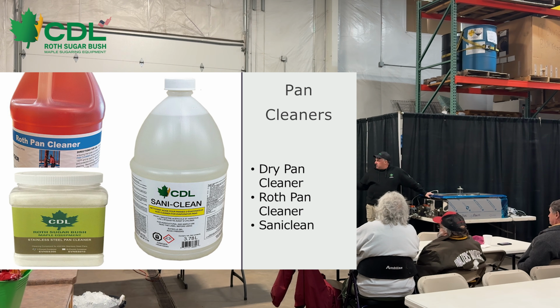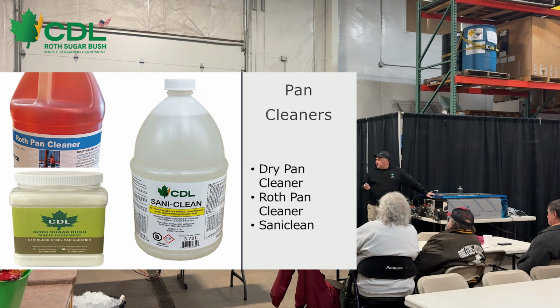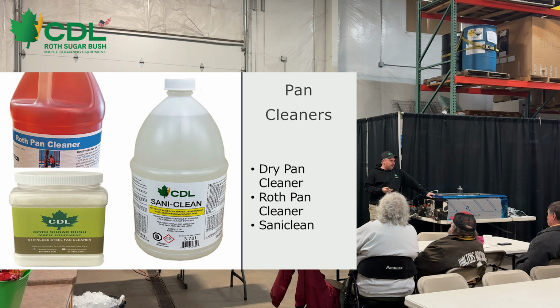We also have another material called SaniClean. This is a bit different formulation of the phosphoric acid. When we put this into an automated pan washer, it won't foam up - if you put the regular pan cleaner into a pan washer, it'll fill the whole room with soap suds. So if you're going to run an automatic pan washer down the road, this is the type of pan cleaner you want to look for. If you're experiencing really heavy niter buildup in your evaporator and struggling to get it clean, and you've traditionally been running the regular pan cleaner, it wouldn't hurt to try some of this. Buy a gallon or two, check it out, and see what you think of the difference. You'll know right away when you pick up the jug.